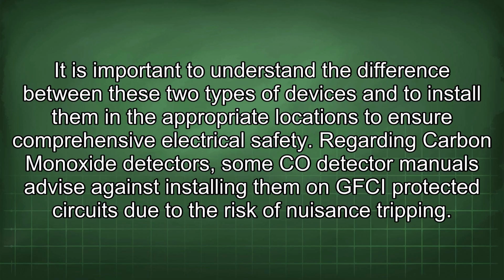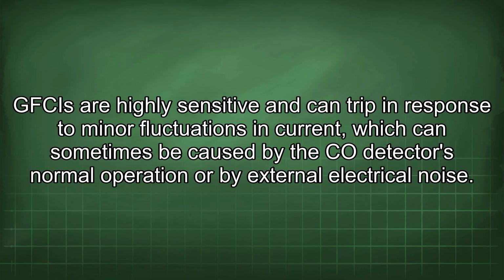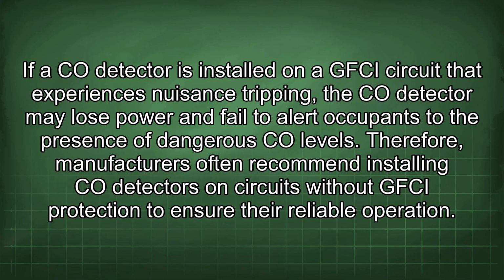Regarding carbon monoxide detectors, some CO detector manuals advise against installing them on GFCI protected circuits due to the risk of nuisance tripping. GFCIs are highly sensitive and can trip in response to minor fluctuations in current, which can sometimes be caused by the CO detector's normal operation or by external electrical noise. If a CO detector is installed on a GFCI circuit that experiences nuisance tripping, the CO detector may lose power and fail to alert occupants to the presence of dangerous CO levels. Therefore, manufacturers often recommend installing CO detectors on circuits without GFCI protection to ensure their reliable operation.